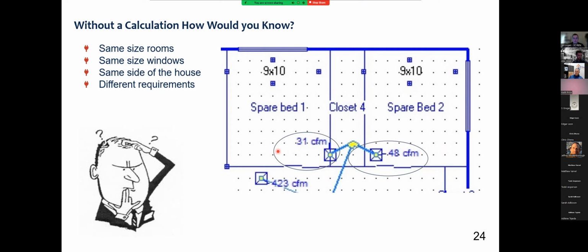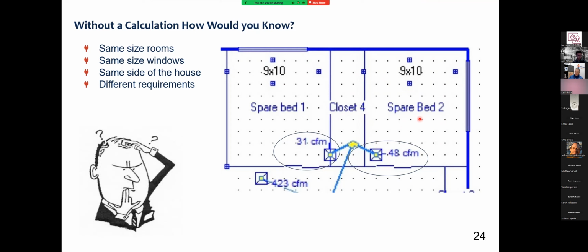If I put a 6-inch duct in both of these rooms and I'm delivering the same or similar airflow to each room, what's going to happen here? This room is going to possibly condition well, and this one will over condition, or this one will condition well, and this one will under condition. So it's really important that we understand these parts of the house that have different exposures need different amounts of air. So when we're putting in systems that run continuously, they might run 1 to 2 hour cycles before they actually cycle the machine off because they're really running at thermal equilibrium most of the time. That's going to give us the air mixture that we need in these rooms to make everything super even, but we do have to get the right amount of air into the rooms.